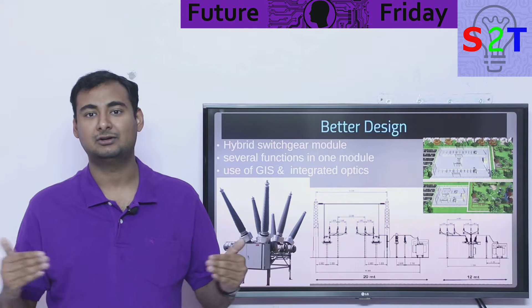We call this a hybrid switchgear module. All that simply means is doing hundreds of things at the same time. The first thing is we use what we call GIS, gas insulated switch. The gas could be anything - SF6, carbon dioxide, or a custom solution. The reason we do this is that an air gap is very good at stopping electricity, however you need a lot of it. Let's say you need two points with 200 kV - those two points must be at least 2 meters apart to make sure there's no voltage jumping across.